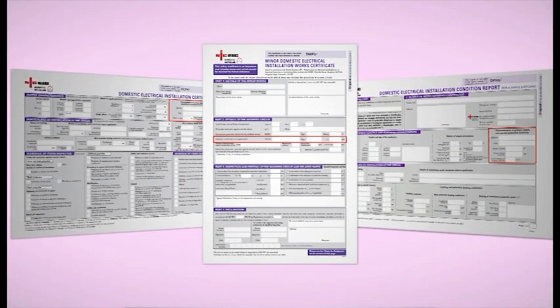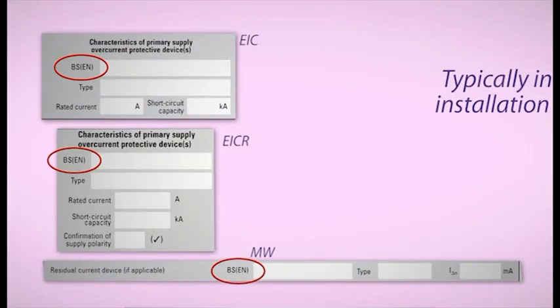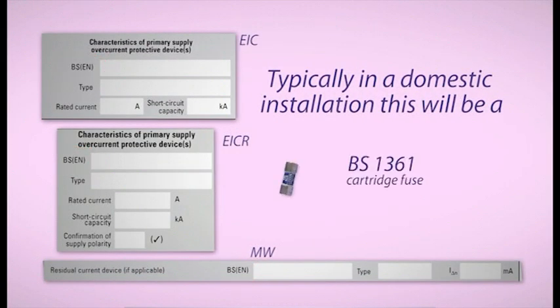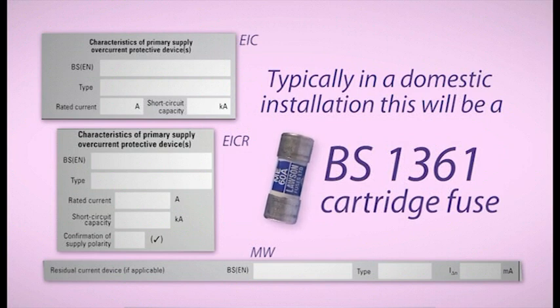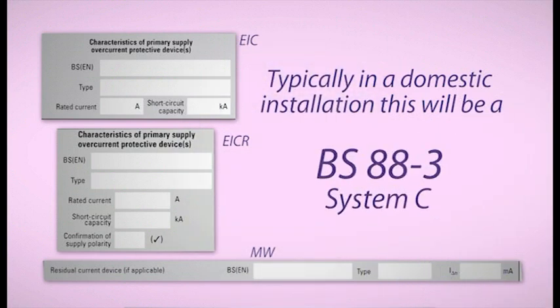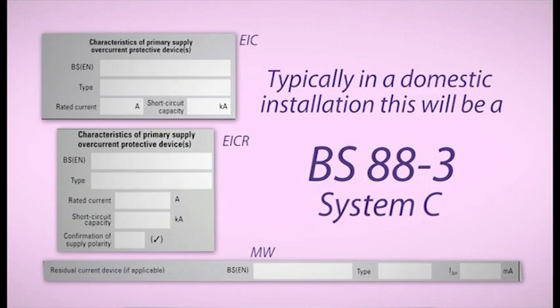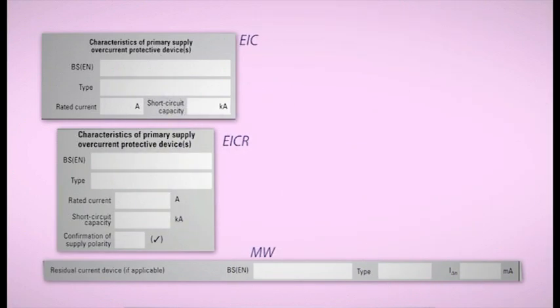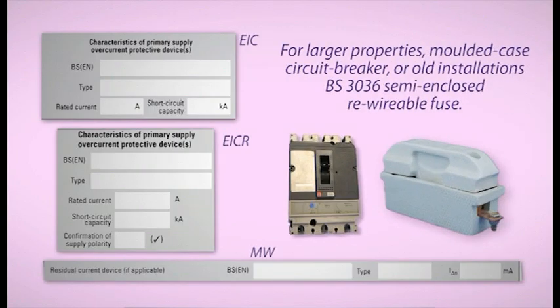Let's look now at the characteristics of primary supply overcurrent protective device. The first box requires the BS EN number for the device. Typically, in a domestic installation, this will be either a BS 1361 cartridge fuse or a BS 88-3 fuse System C, which was introduced with Amendment number 1.